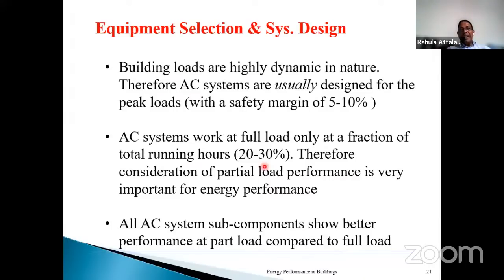All mechanical equipment, that is chillers, boilers, compressors, even automobiles, that's the internal combustion engine, will operate efficiently not at the full load, but at part load. Most of the air conditioning devices will be more efficient between 60 to 80% somewhere there than at 100% load. So when we size an equipment, if you have an equipment slightly oversized and expect the building to operate in the 60 to 80% of that equipment sizing, then we can expect the equipment to operate at a higher efficiency than working on the full load.